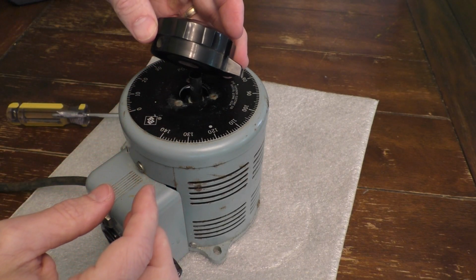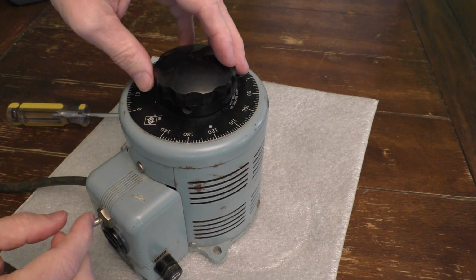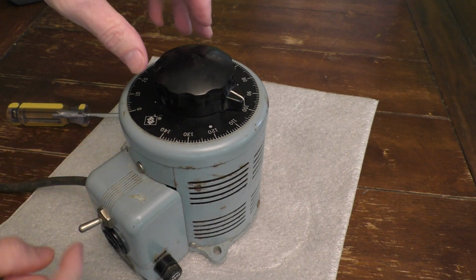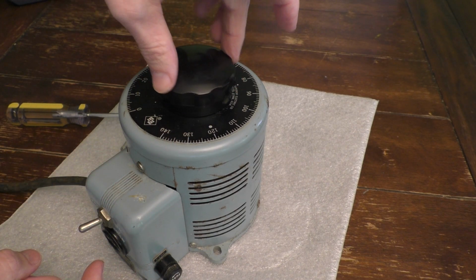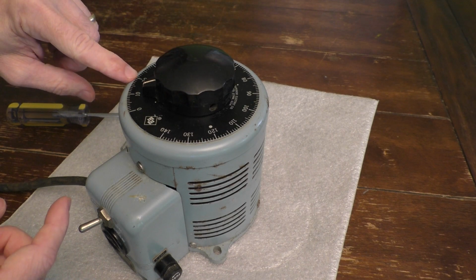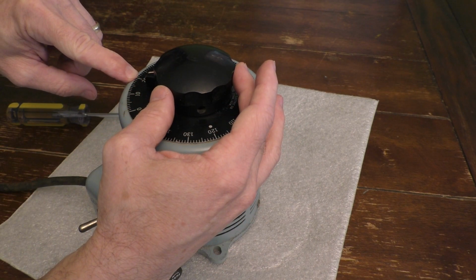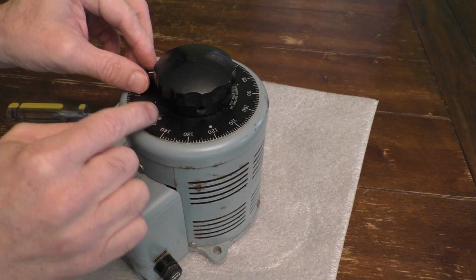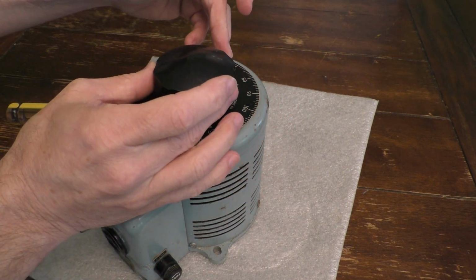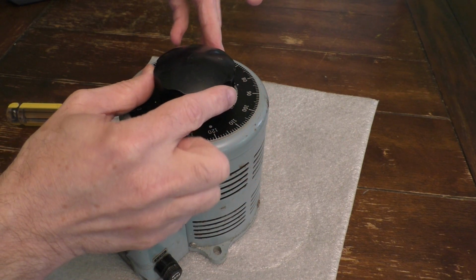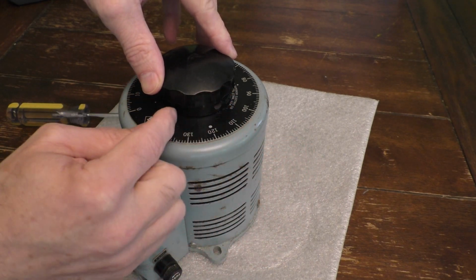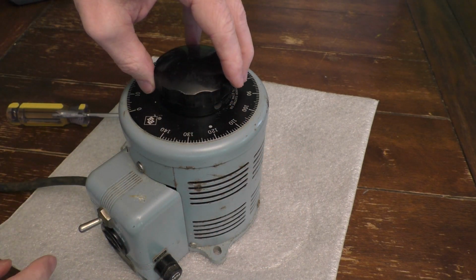When you replace this, you want to test it out, turn it on, and use your multimeter to make sure that if you're measuring 20 volts, it's in the right position. I calibrated it to the 60, so I set it to the 60 volts and then tightened up these screws. That's how you put this cap back on.